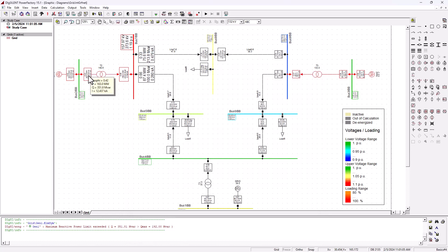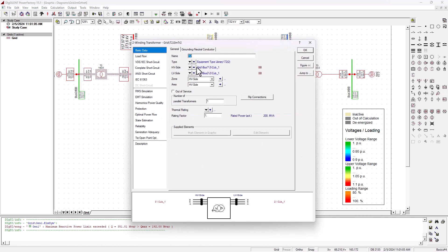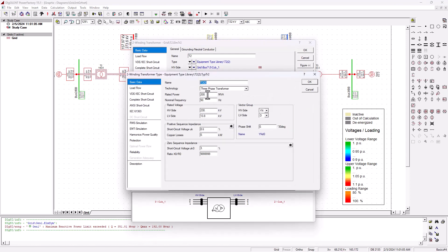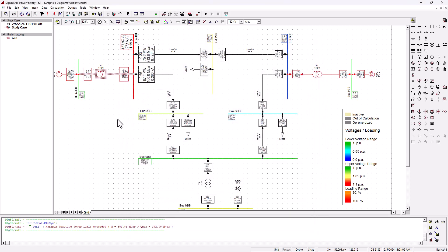We come to the type here. We can see that this transformer is 200 MVA. That's the rating of the transformer. But when you look into the primary, the power coming on the primary, there is 163 megawatt and we got a reactive power of 351.8. If you do the sum of that, basically if you calculate your S using your P and Q, you're going to get a value that is way above the 200 MVA that the transformer is rated for.